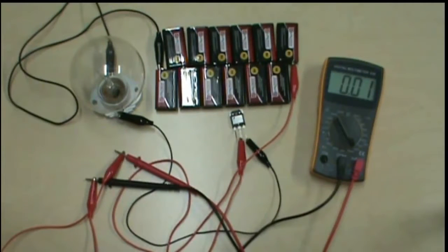And as I said, it's not a normal mode of failure for an IGBT to necessarily leak. The only DMM check, or digital multimeter check, you can do on one for the most part is to check for a short between the collector and the emitter. And so if you use your meter and find out you've got a short, that's about all you can do with a DMM.